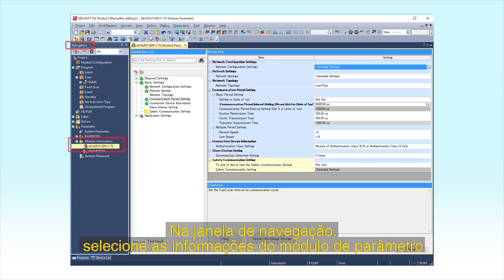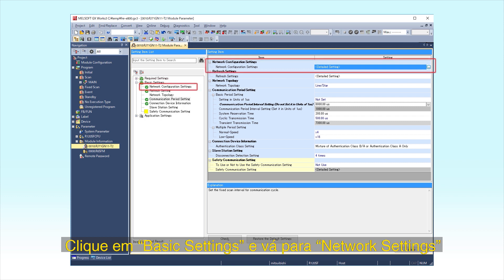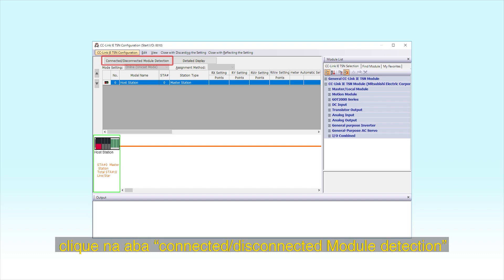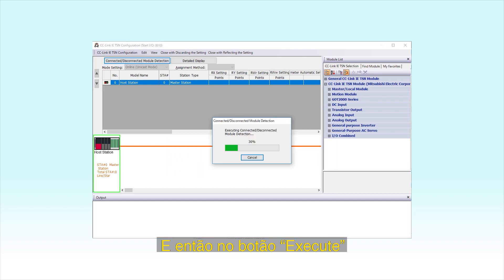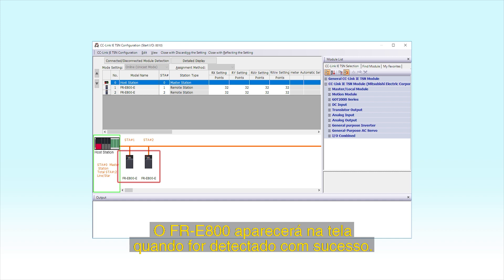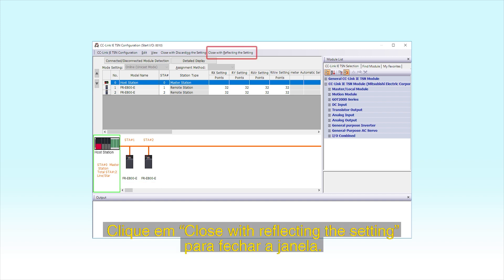In the Navigation window, select Parameter, Module Information, and then double-click RJ71GN11-T2. Next, click Basic Settings. Go to Network Configuration Settings and click on the button with three dots next to the Detailed Settings field. Click the Connected/Disconnected Module Detection tab in the CC-Link IE-TSN configuration window, then click the Execute button. FR-E800E will appear on the screen when it has been successfully detected. Click the Close with Reflecting the Setting menu to close the window.